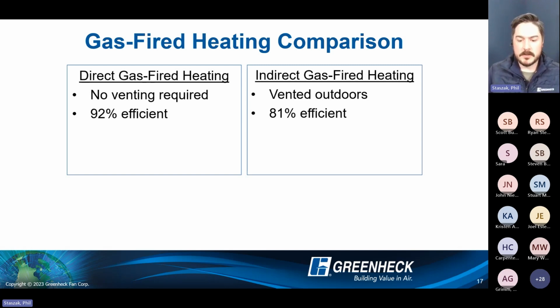Fun fact as far as efficiency goes on indirect gas-fired heat: you get more efficiency by putting more stuff in the airstream to reject more heat. Putting more stuff in the airstream takes that efficiency gain from what you're burning gas at and transfers it over to the motor on your fan side, because you typically have more to overcome on a higher efficiency furnace. So that's one other conversation piece on why we limit efficiency on the indirect gas fired side, and why we don't really see the push toward higher efficiency, like the 92% efficient on the direct gas fired side.